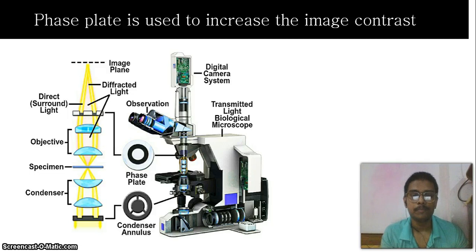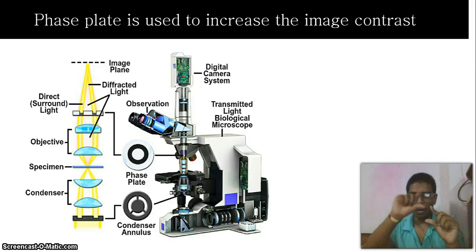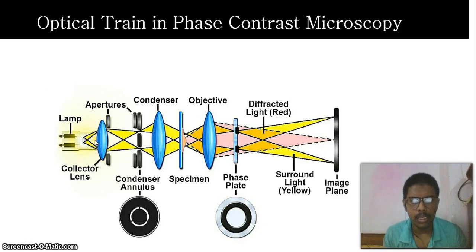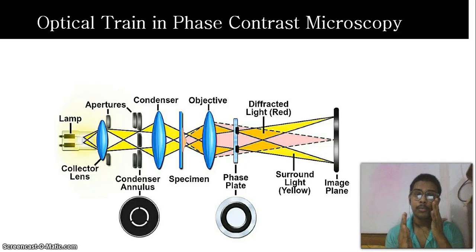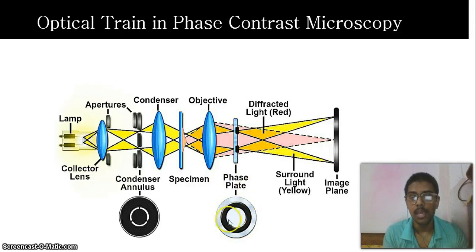Now to see the optical train — the optical arrangement showing the ray of light throughout the whole microscopy system — you can see here is the lamp as the light source. The condenser lens is exactly the same as in dark field microscopy: it contains a special type of lens which doesn't allow the central part of the beam through. Up to the objective lens it is exactly similar to dark field microscopy, but additionally the phase plate is used — this is the special thing in phase contrast microscopy — and the phase plate makes a phase difference.